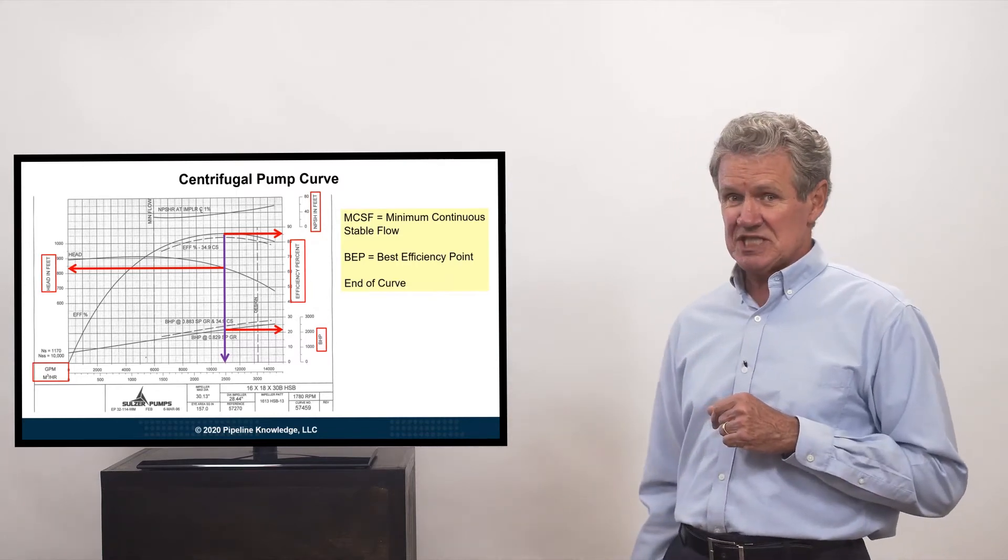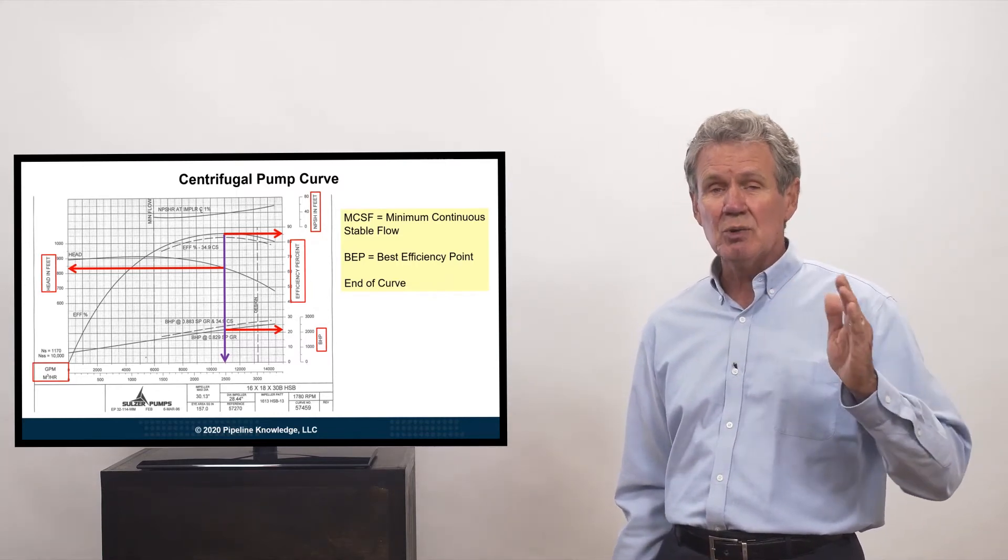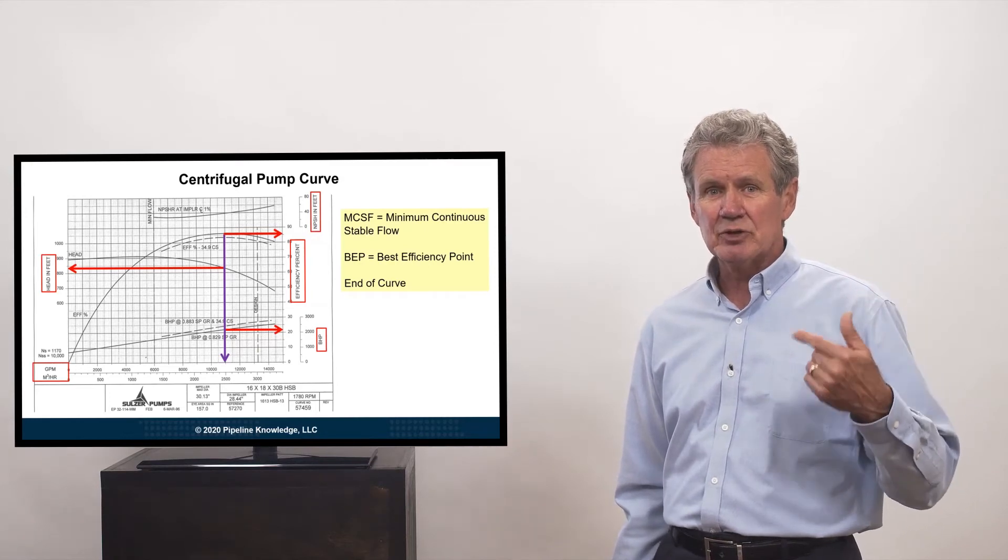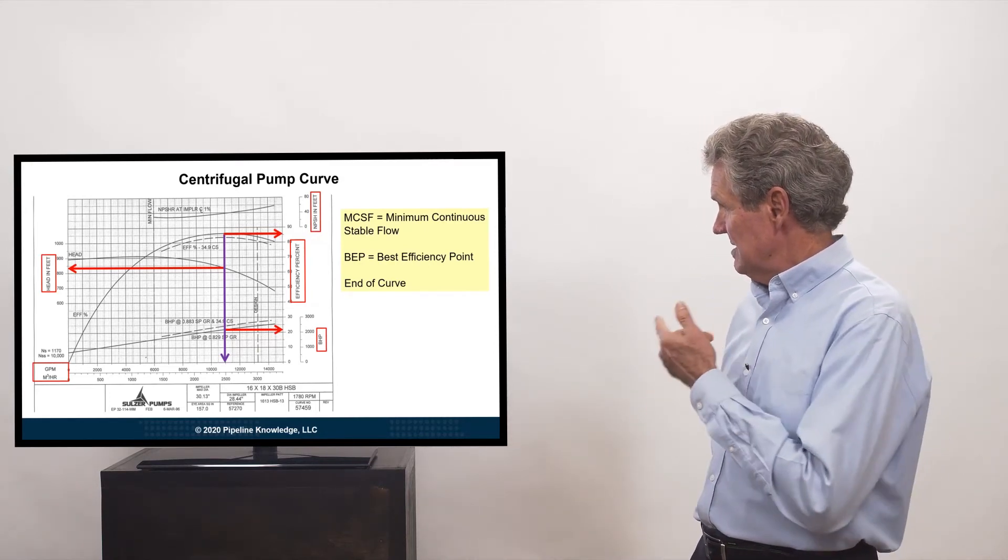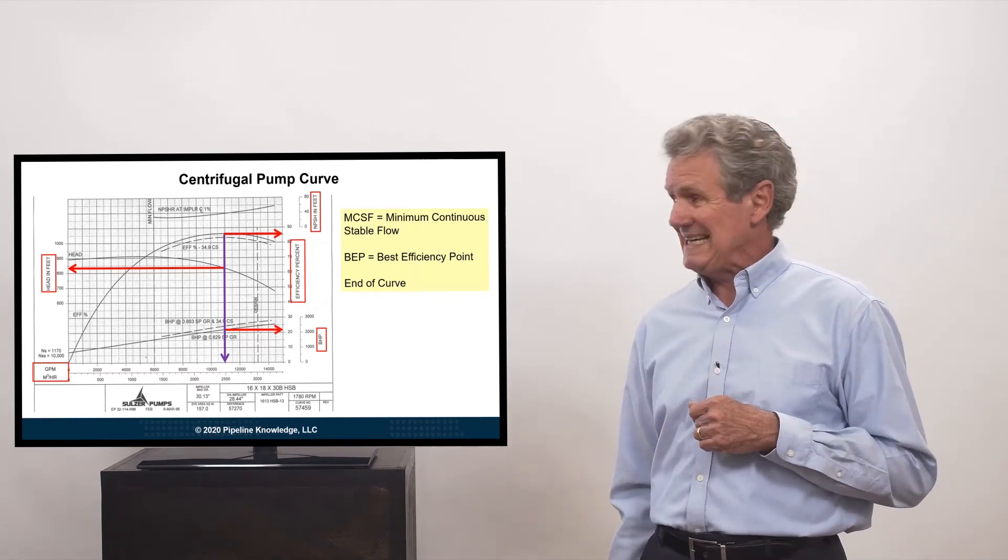I'm going to show you a couple more things. The minimum continuous stable flow. If we go too low in flow, the flow pattern through the pump gets messed up and is not effective. The best efficiency point and the end of the curve.